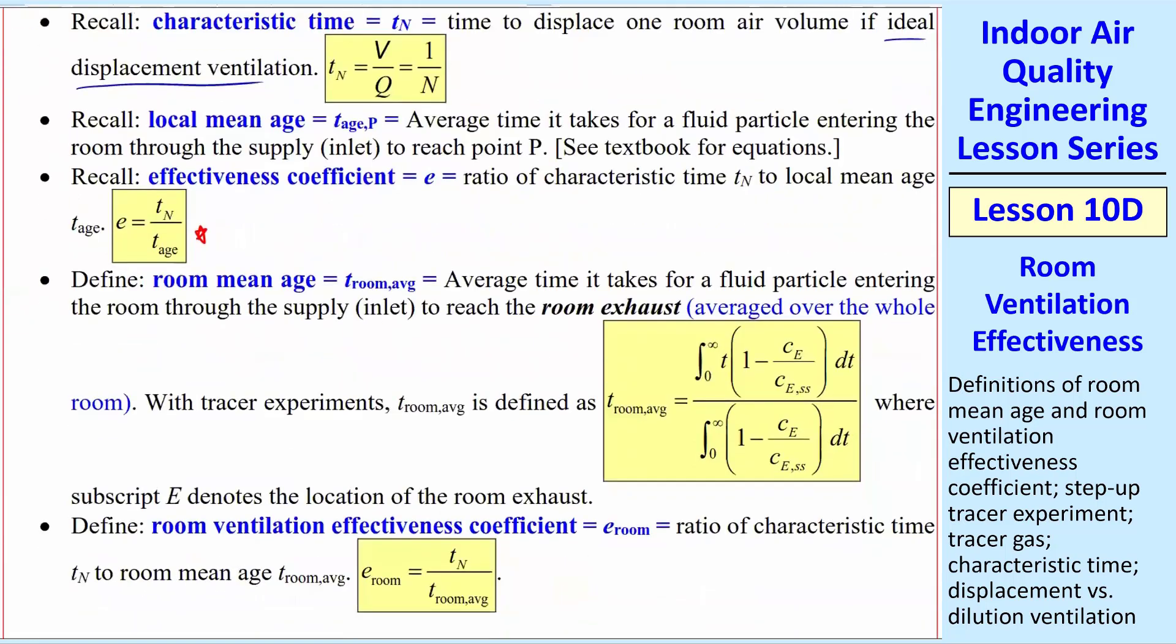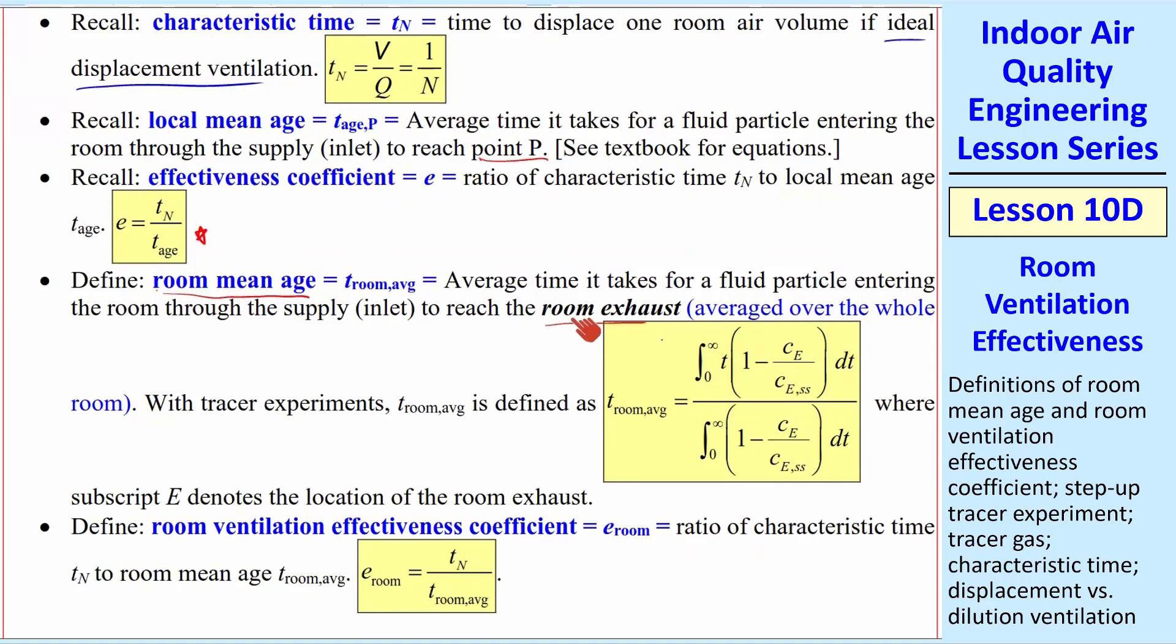Now we're going to define this T room, average, or room mean age, which is a similar kind of thing. An average time it takes for a fluid particle entering the room through the supply to reach the room exhaust instead of P. This was point P, this is room exhaust, but otherwise it's the same. The difference is it's averaged over the whole room. It's a global property, as I said, because everything ends up going to E.